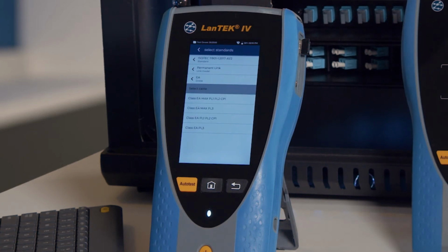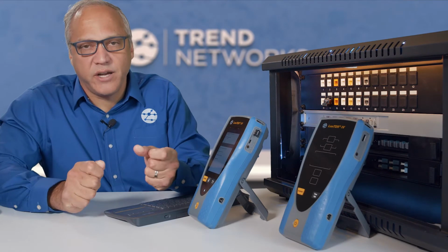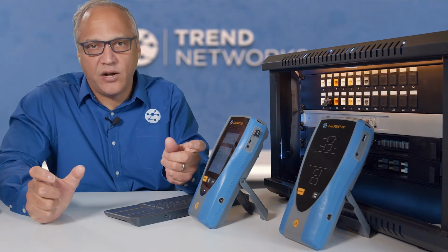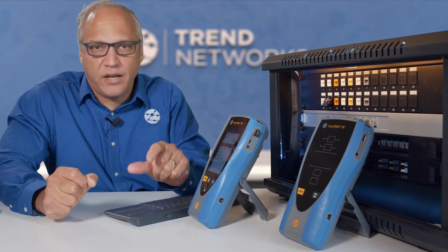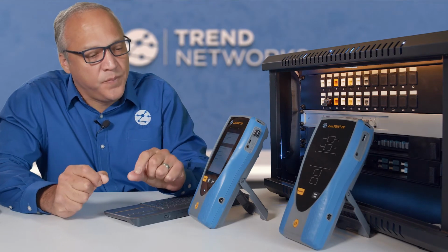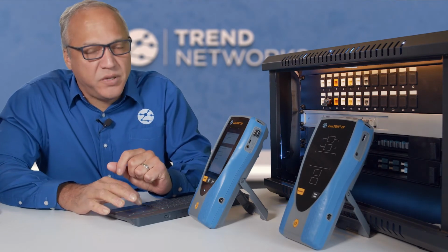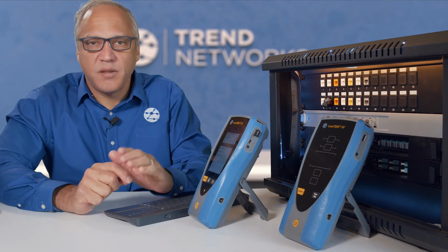Now, once we get down here, we have several choices. We have EA Max, PL1, PL2, CP1. So this is the most typical configuration where you're going to have a patch panel and an outlet at one end, and you can have a consolidation point in the middle. And max means that we are going to run all of the possible tests.